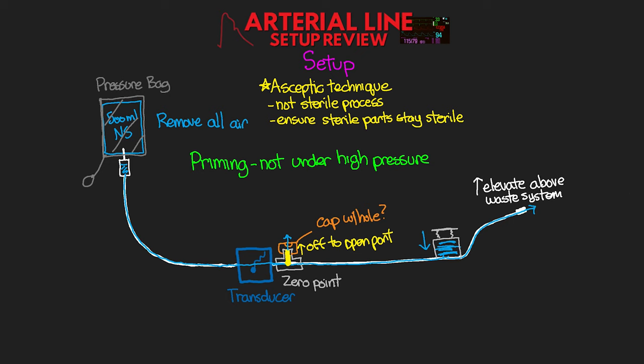Now, if you are using a setup without the built-in waste system, we are going to need to flush to the end of the system. So if you have another three-way near the patient for access, we're going to treat this one just like the zero stopcock. So turn this stopcock off to the patient or the open end of the tubing, remove the cap if no hole is present, prime until saline exits that open port, replace the cap if you had to remove it, turn the stopcock off to the open port, and continue priming until saline exits the end of the tubing.